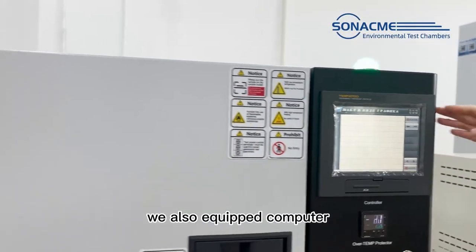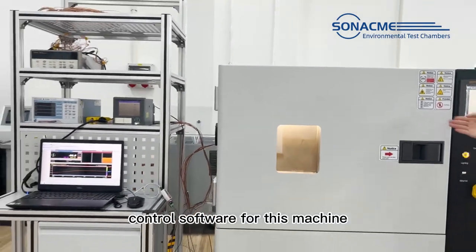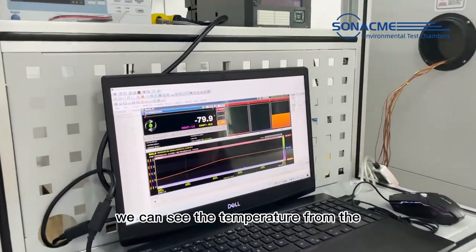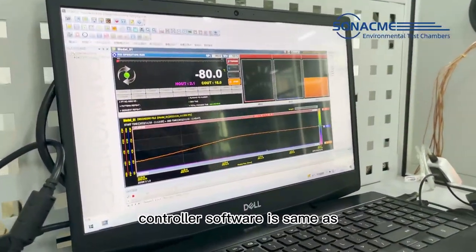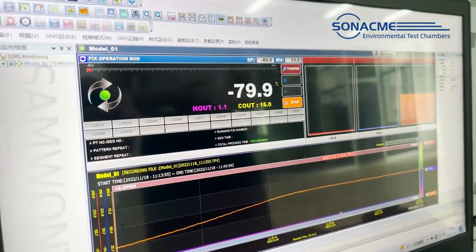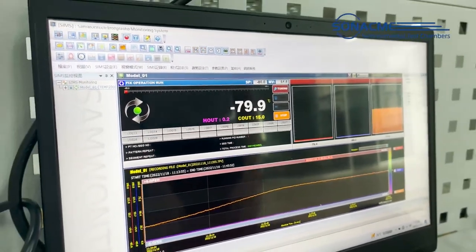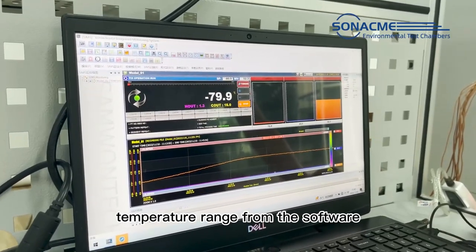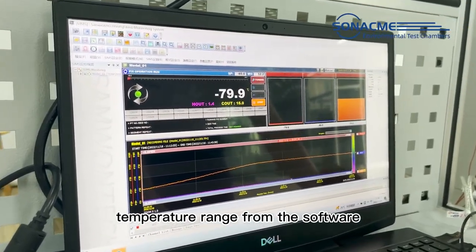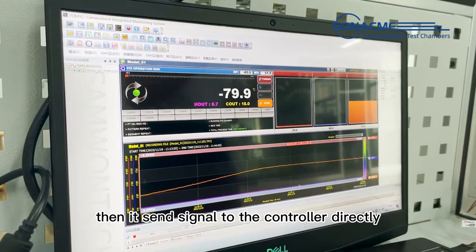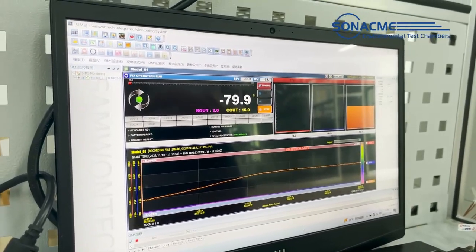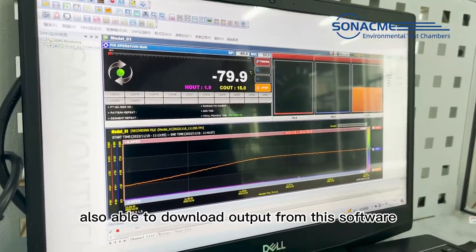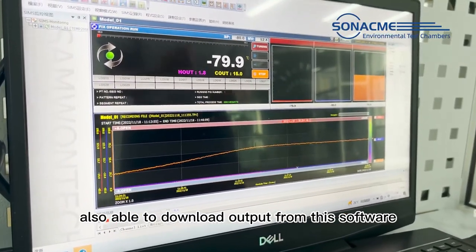We are also equipped with computer control software for this machine. We can see the temperature from the controller software is the same as displayed on the screen. We can also set the set point and set the temperature range from the software, and it sends the signal to the controller directly. The testing data, testing history, and curves can also be downloaded and exported from this software.